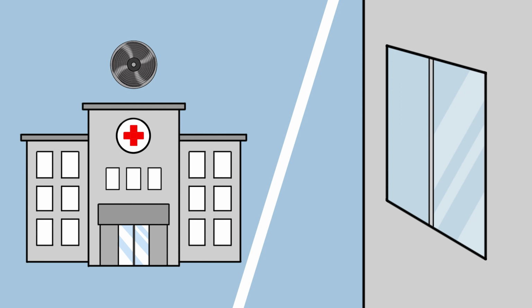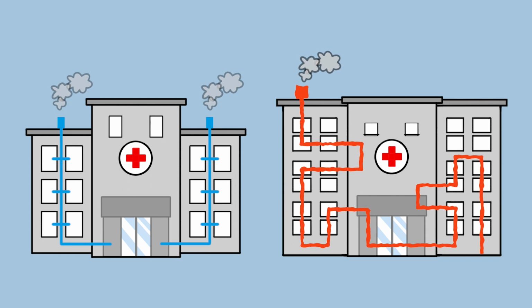fan serving other rooms and increase that fan's motor size. A simpler solution may be to install a HEPA-filtered fan or negative air machine and blow the air directly outside through a window. However, if an existing facility is converting a room to negative pressure to have additional capacity, for instance, in the event of a surge in patients requiring negative pressure rooms, exhausting to the outside may be challenging.